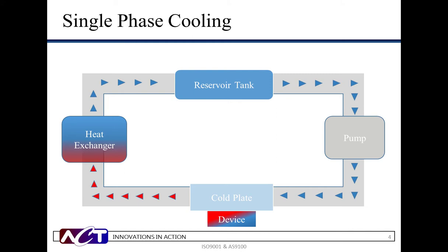As the fluid is pumped through the cold plate, heat is exchanged from the critical component to the liquid. Higher heat flux components require a faster flow rate to absorb the increase of thermal energy. High-performance liquid cold plates with embedded tube, mini-channels, or micro-channels have been designed and manufactured. These designs are optimized to reduce pressure drop and increase flow uniformity, as well as maximize heat dissipation. However, even with expert designs, single-phase cooling fails to keep up with the harsh thermal environments of more innovative challenges.